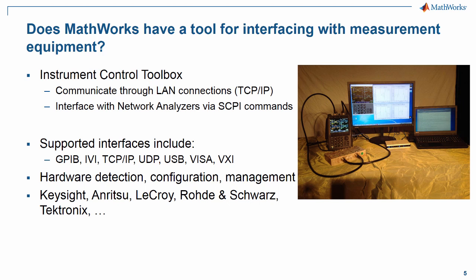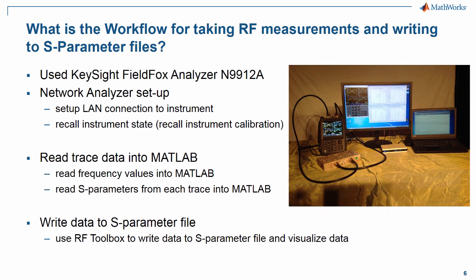The Toolbox has built-in commands so you can easily interface with the network analyzer and use SCPI commands to recall instrument states, read data from individual traces, and put the instrument back into a desired final state to continue measurement work. The first step is to connect an actual microwave component to the network analyzer — in this case a high performance microwave cavity filter. Next, we open the network interface to the network analyzer so the MATLAB script can control the analyzer and extract network parameter data.